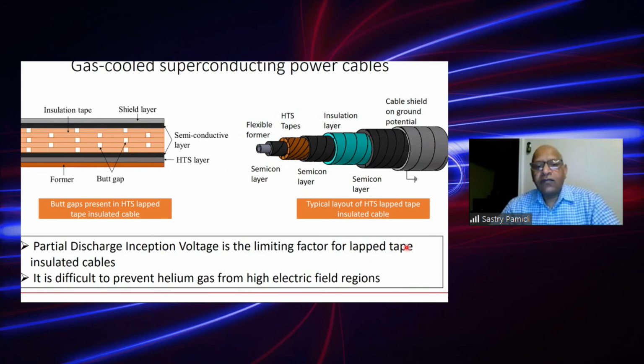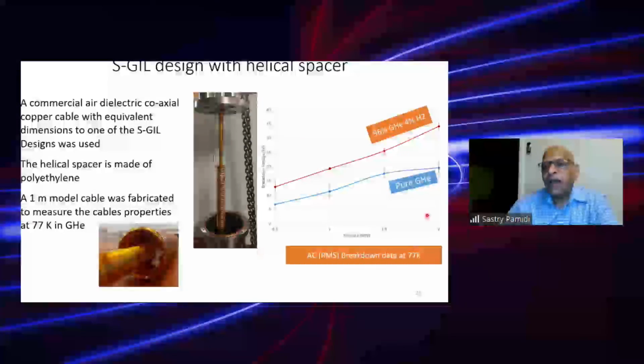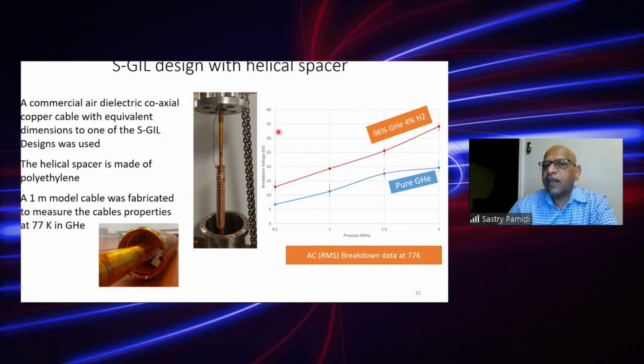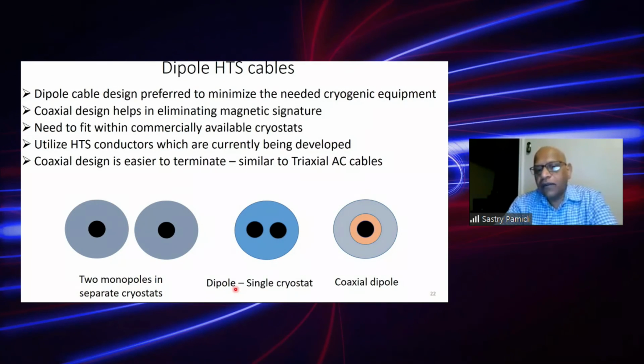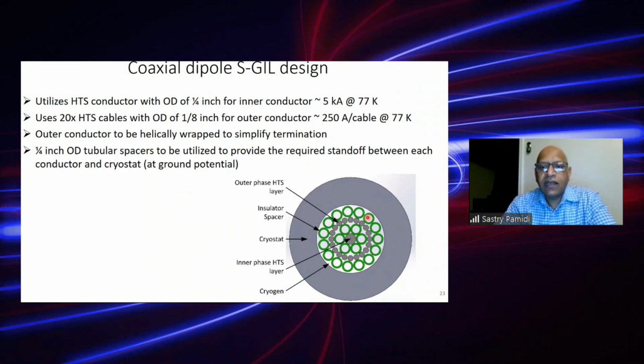As I said, one of the challenges with helium gas cooled devices is dielectric strength. In this design, if I use a helium hydrogen mixture, we can reach 35 kilovolts at 2 megapascals. The sizes of this cryostat and the conductor are similar to what we use in critical applications. We can also build dipoles. We can use 2 single poles or 2 cables in one cryostat like the dipole we tested before, or we can use a coaxial dipole. We also have been working on superconducting dipole cable designs. So you can design the dipole in multiple ways.